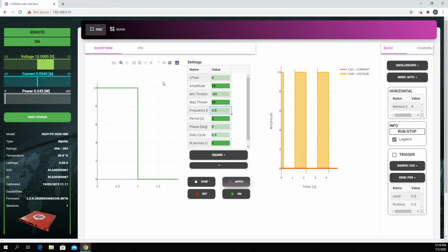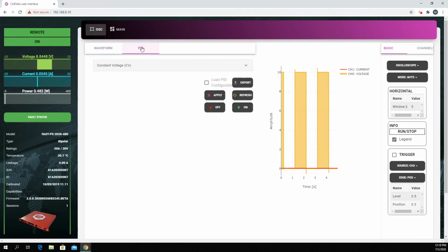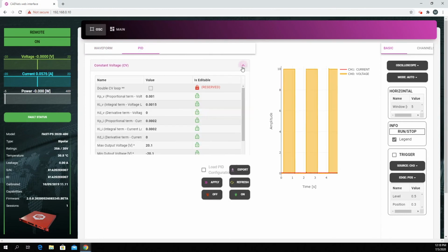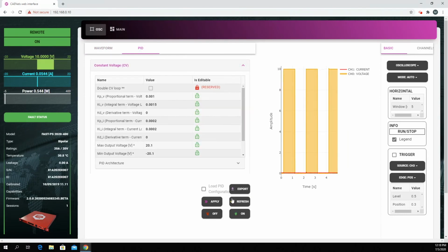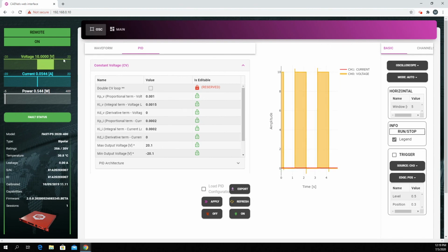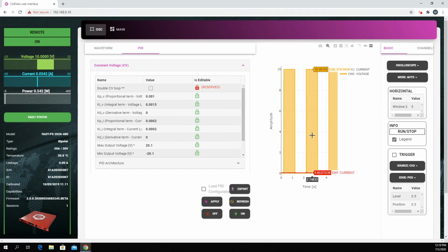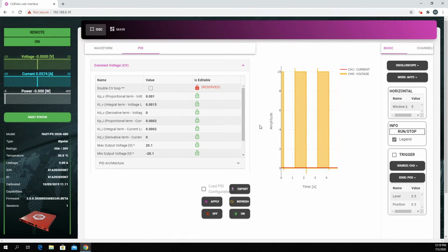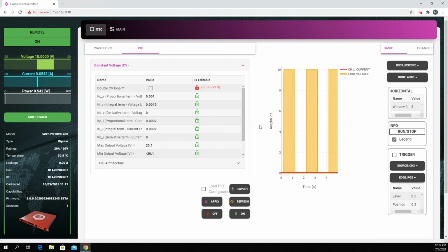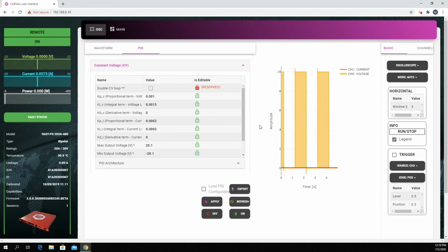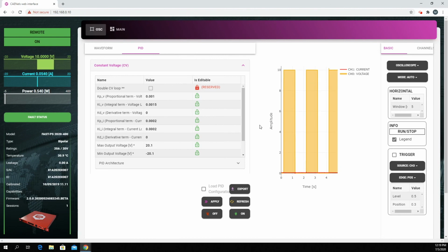And this is what one would be able to use to tune the unit with a load connected. And now it would allow us to enter in the values and to apply them. And while the square wave continues, we would see changes in the output corresponding to the reactance of the load. And so this is a great way to tune the unit. That said, pretty soon we'll take it even further with an auto-tuning feature that will be built in, and none of this will be necessary, although it will be available for fine-tuning if one would like to do so. But the auto-tuning will allow someone to connect the unit to their load and the unit will tune itself.